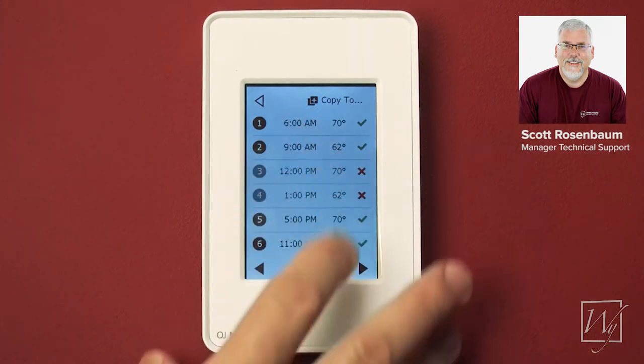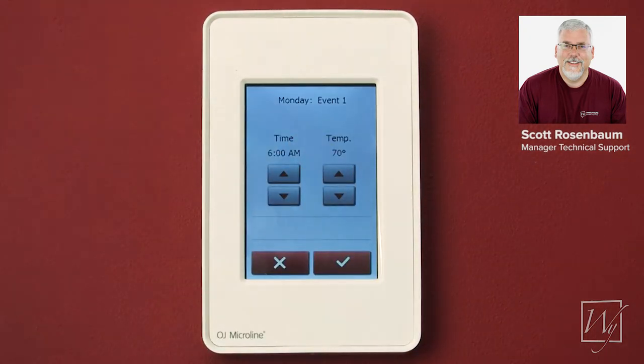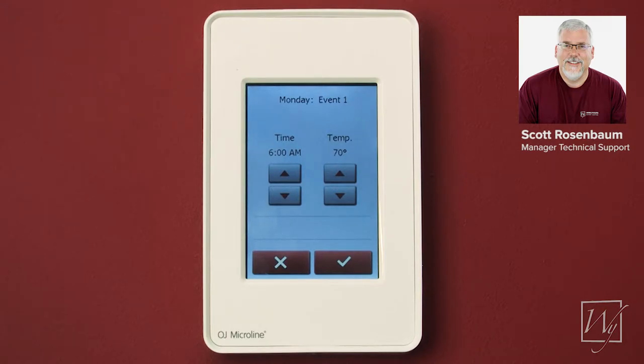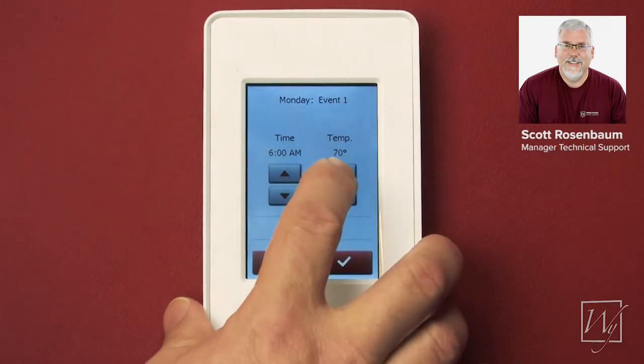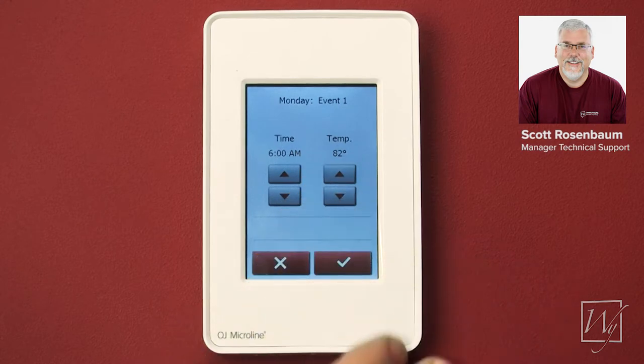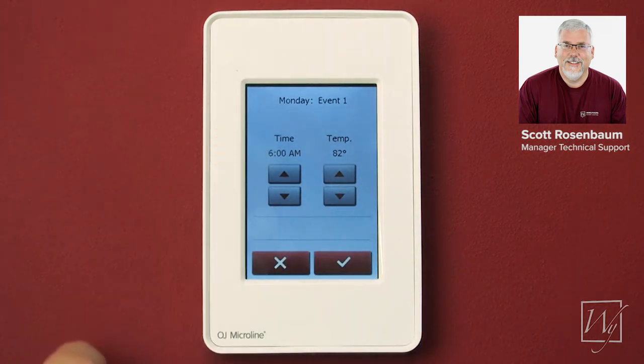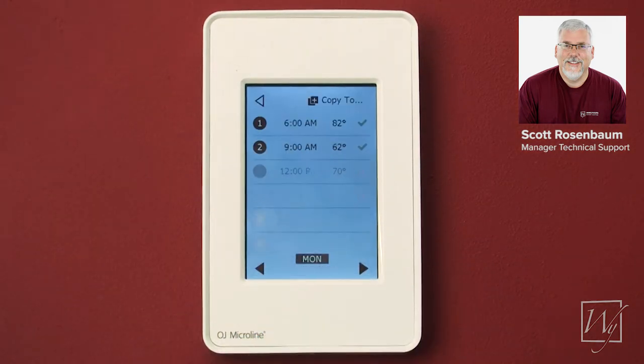Let's say I like the 6 a.m. time but I want it to be warmer. Most people choose 82 degrees — you can make it whatever you want. We're going to set it for 82, and remember that temperature is for the floor, not for the ambient air temperature — it's the floor temperature itself. So I'm going to set this to 82 degrees at 6 a.m. and press OK.